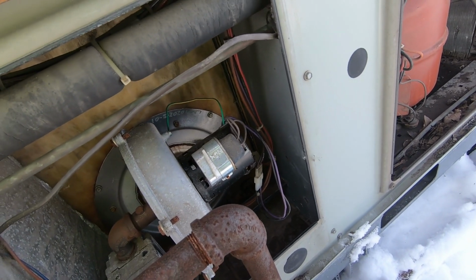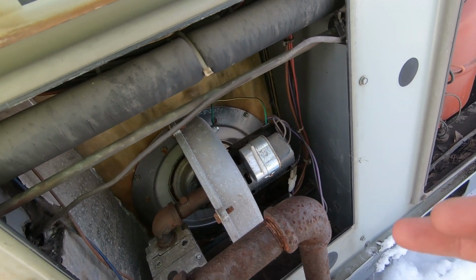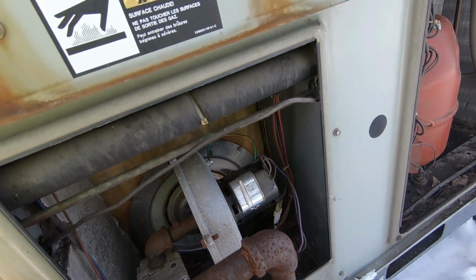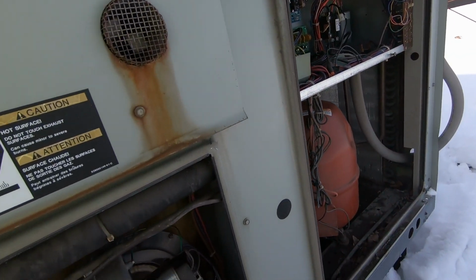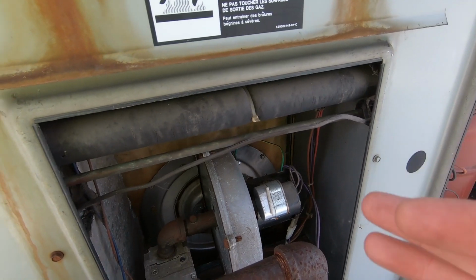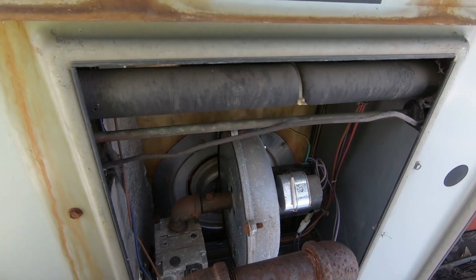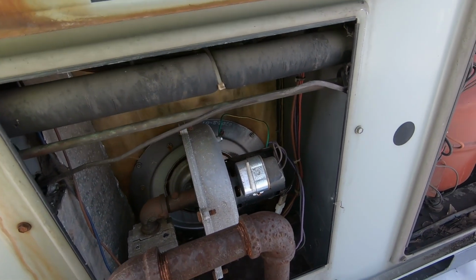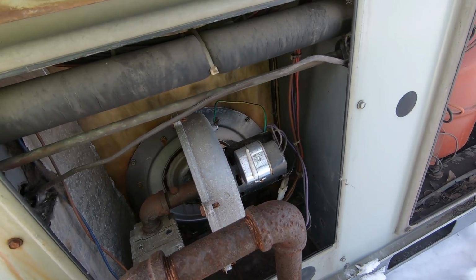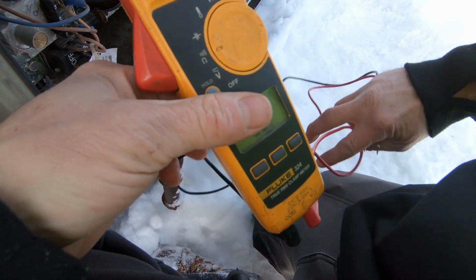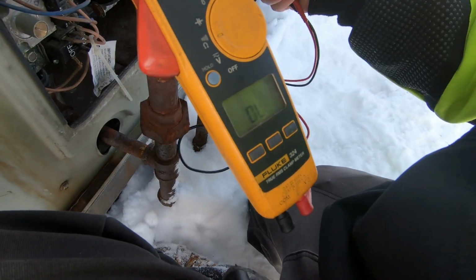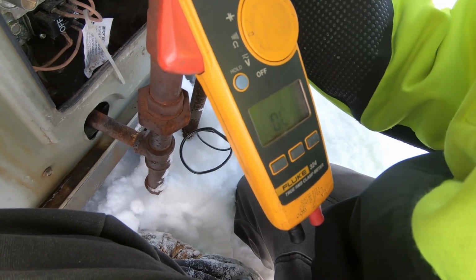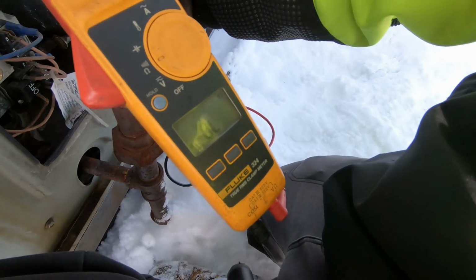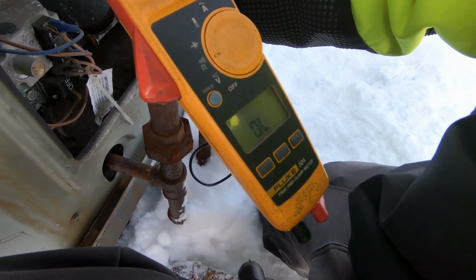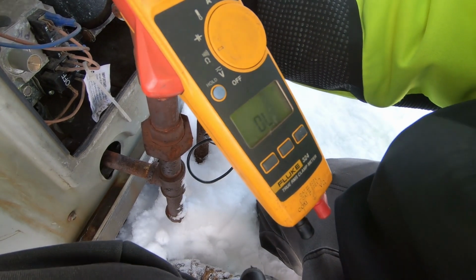I'm doing an ohm reading on it. So the igniter's no good. Combustion blower's no good. Heat exchanger's in decent shape. Blower motor's running. All the electrical looks good. So we're gonna write up an igniter, a combustion blower, and come back to repair. Let me set this down, get you that ohm reading. Not the most ideal setup here. I'm not going to be able to show you both, but let me get on there and see if I can balance this camera on the meter.